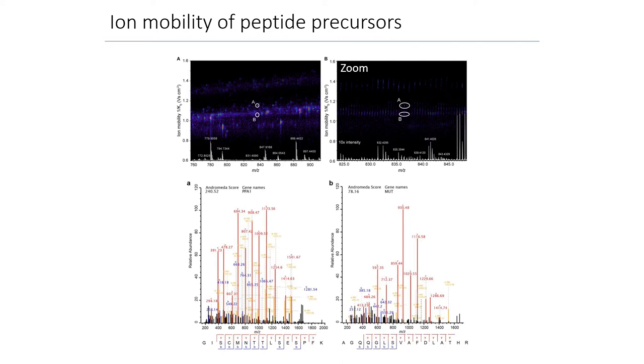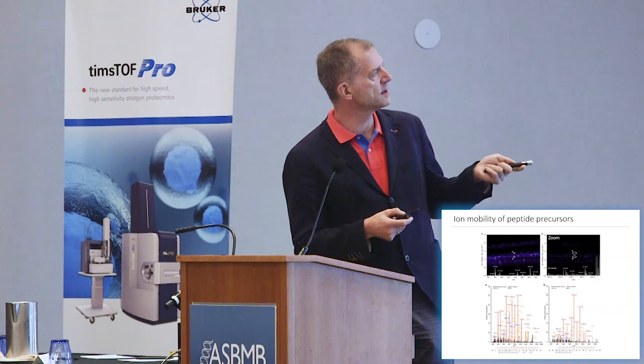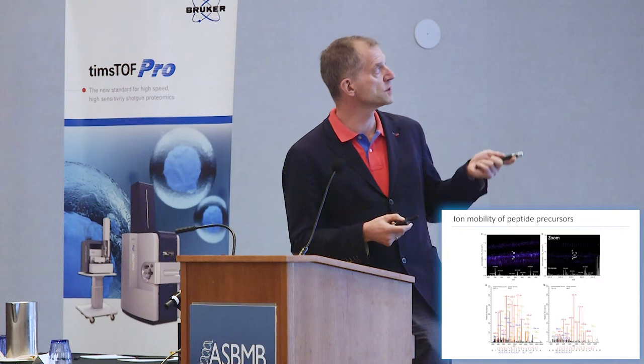Here's an illustration. In the ion mobility dimension and the MS/MS dimension, there are co-eluting ions — precursor ions that have the same mass — that project onto the same precursor in a normal MS spectrum without ion mobility. But now we know this and can catch the ions: one in one scan, another in another scan, giving completely different MS/MS spectra. You can catch both, which would have been hard otherwise — these would have been chimeric spectra.